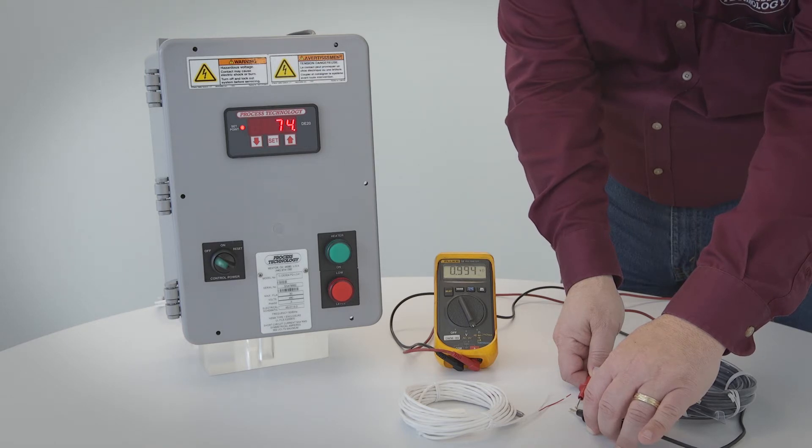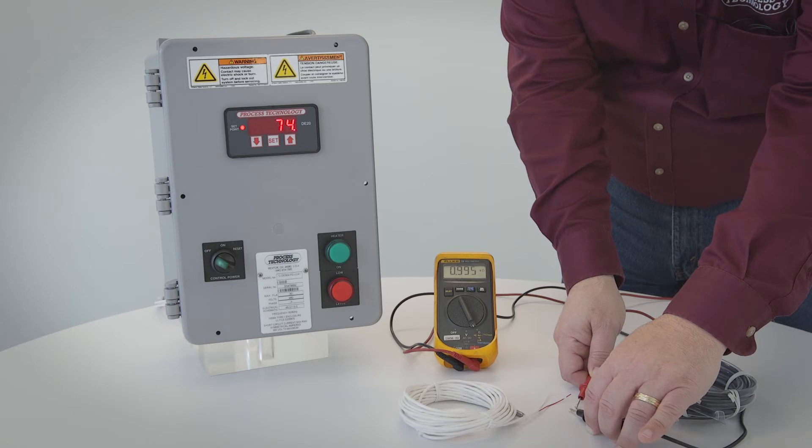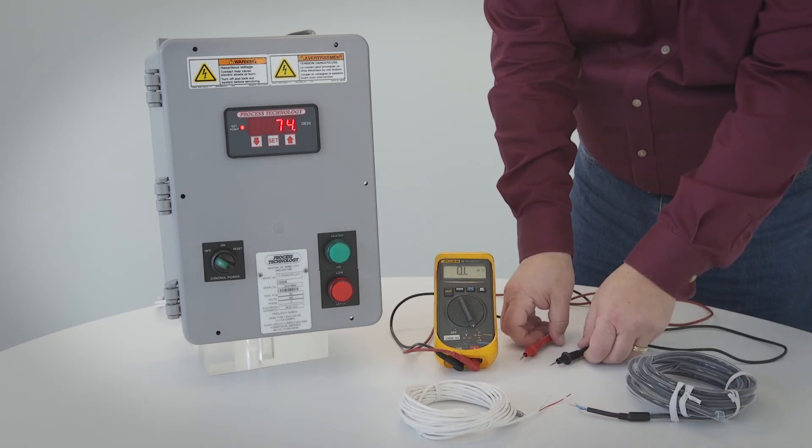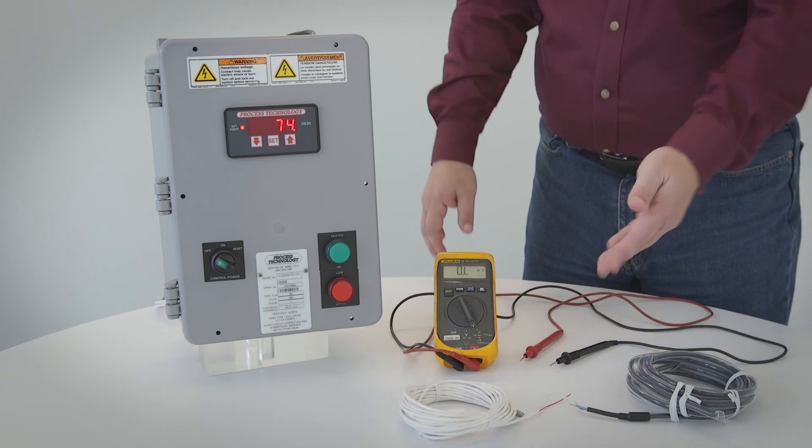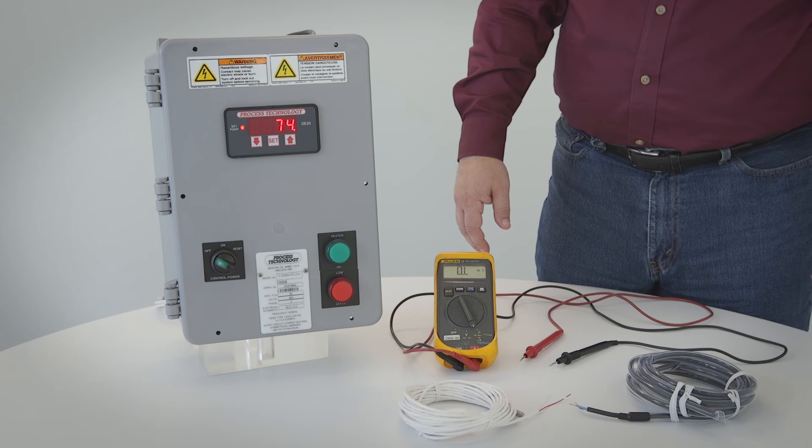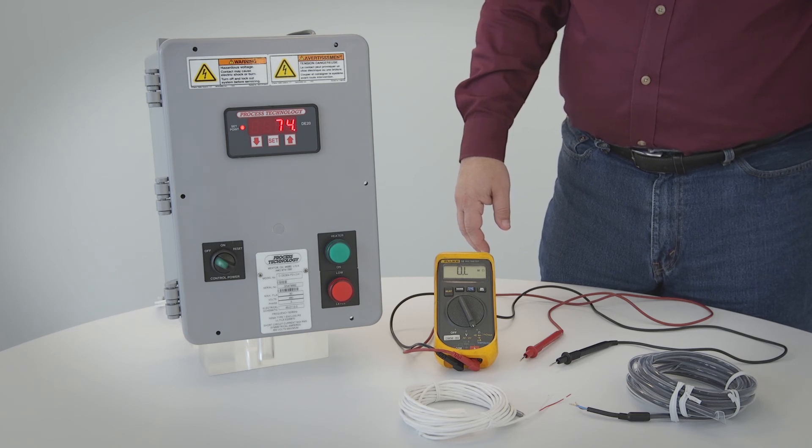Don't get concerned about the exact number. Just see that the measurement is around the expected value and that the reading is a nice steady number. A resistance measurement that is very far off or a measurement that is erratic indicates a bad sensor. Then the temperature sensor should be replaced.